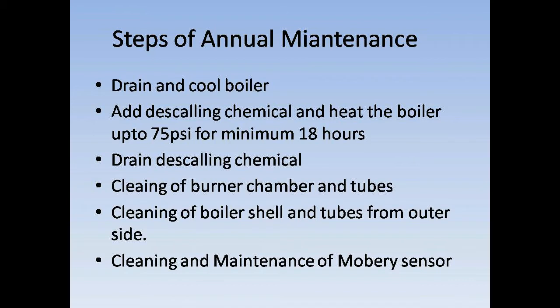After draining the descaling chemical, we have to clean the burner chamber, the burner tubes from inside and outside, and also the boiler shell. At last, we have to clean the boiler's Mobrey sensor, which is very important for safety purposes.